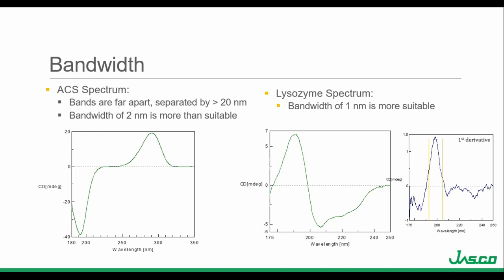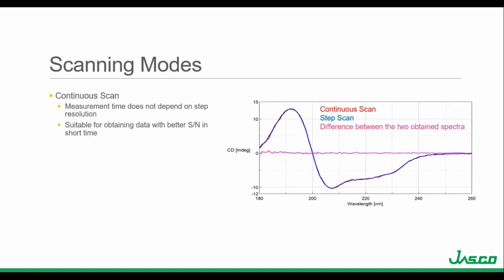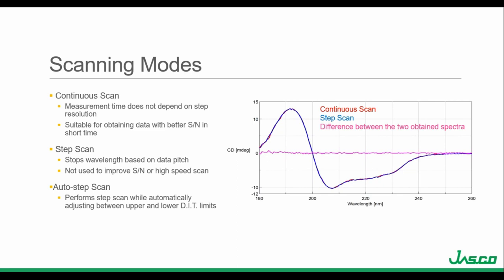The standard spectral bandwidth for CD measurements is 1 nanometer, but for high sensitivity measurements, the bandwidth can be adjusted to 2 nanometers to improve signal to noise because you get more light throughput. JASCO offers three different scanning modes. The continuous scan acquires a CD signal at each wavelength while moving across the desired wavelength range — this mode can be used to obtain data with better signal to noise in a shorter acquisition time. The step scan mode stops the monochromator at each wavelength based on the data pitch, making it much longer. The auto step scan mode performs a step scan while automatically adjusting the digital integration time for a constant signal to noise ratio.